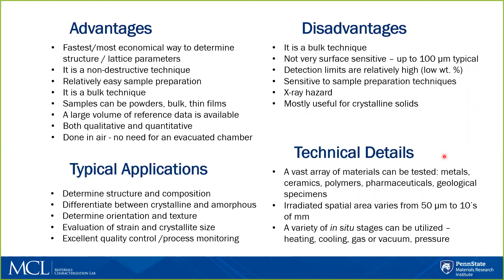Some technical details: you can measure a vast array of materials, including things like metals, ceramics, polymers, pharmaceuticals, and geological specimens. Our irradiated spatial areas vary from a low of perhaps 50 microns on a micro-diffraction instrument up to tens of millimeters on a conventional powder diffractometer. There are a variety of in-situ stages available, including heating, cooling, gas, vacuum, and pressure.